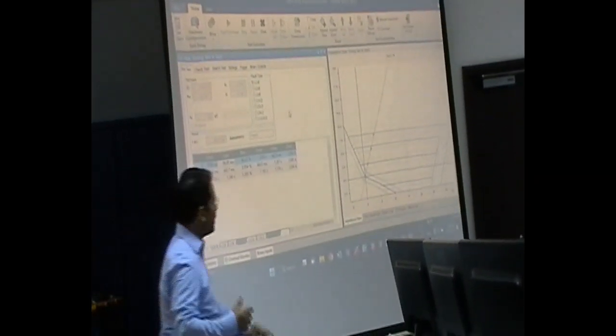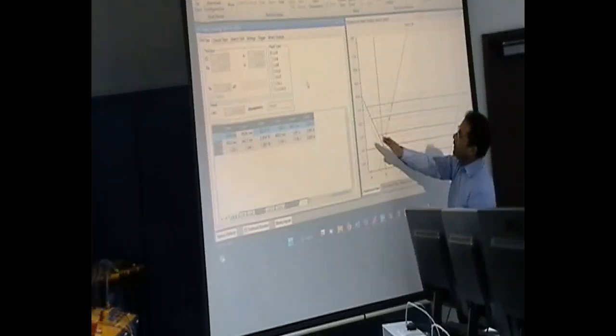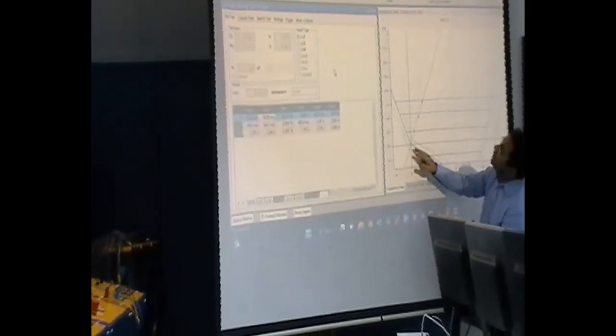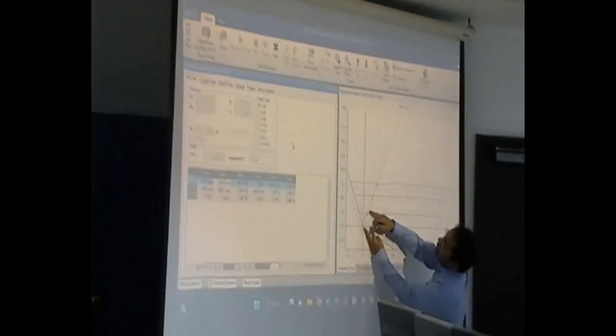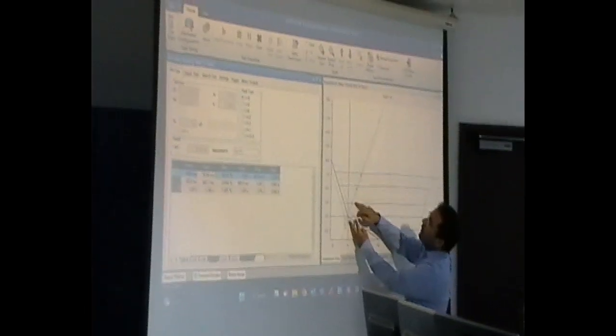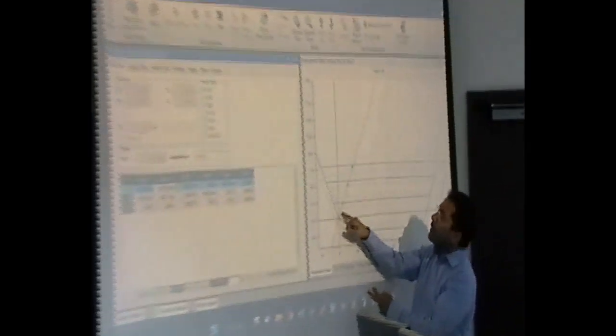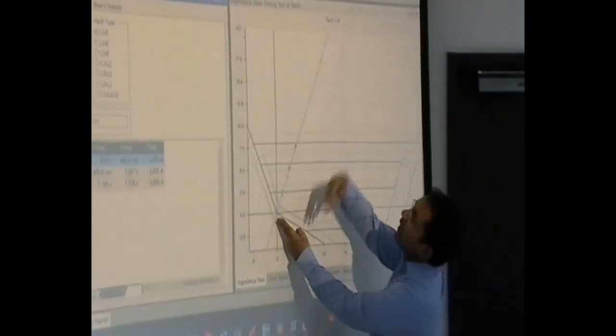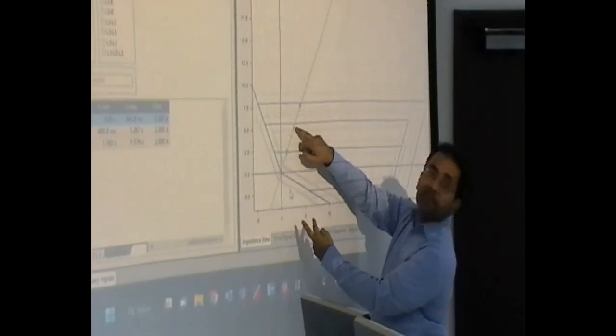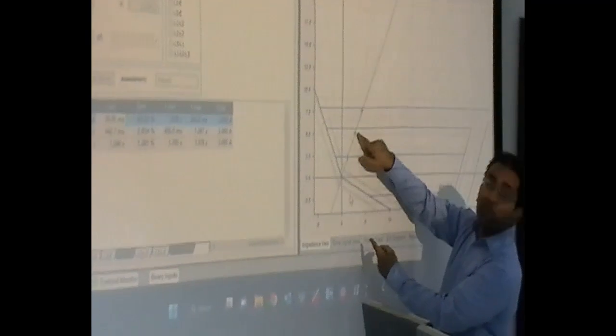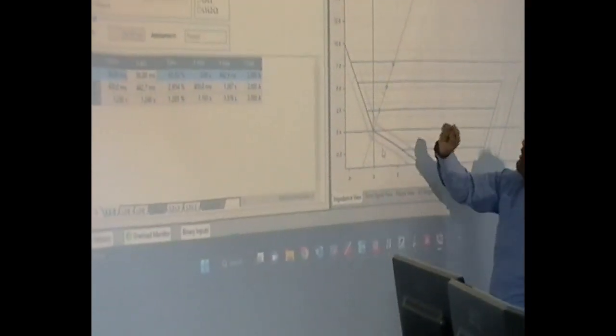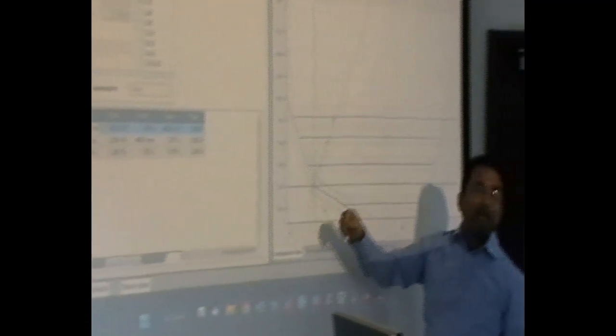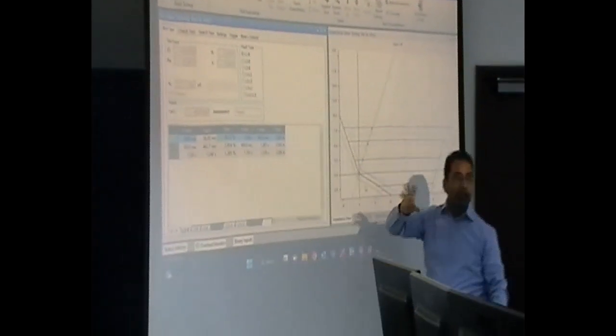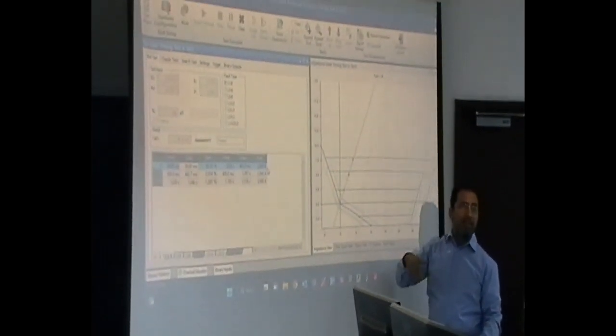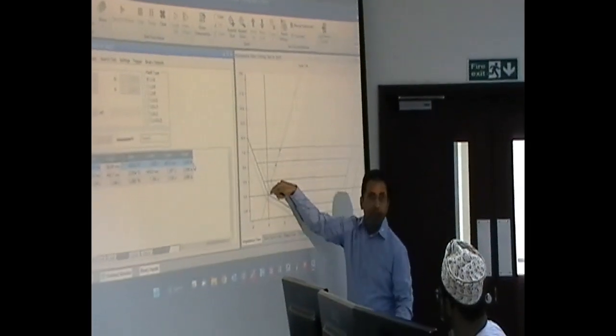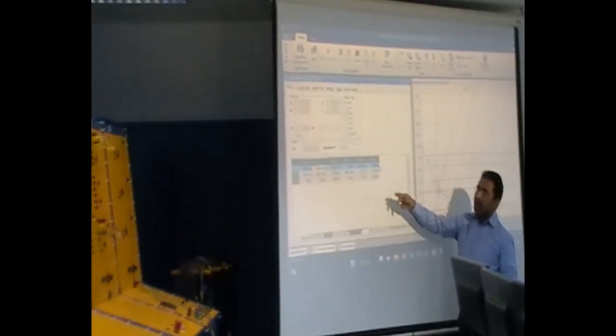So we have the line, this is the line, and we have our substation here, and this is the next substation. You are protecting, for example, 80% of the line. If the fault is in this region, zone 1 should operate. If it's in the next substation, that is zone 2, and a fault inside zone 2 should operate. Then this is zone 3. So when you click here or put the point here, the test set will inject some current and reduce the voltage to see the under-impedance part, so that the impedance goes directly to this point. Then it will measure the operating time.